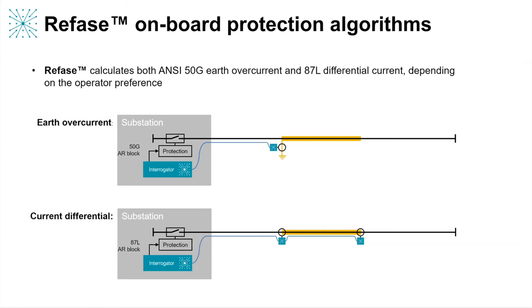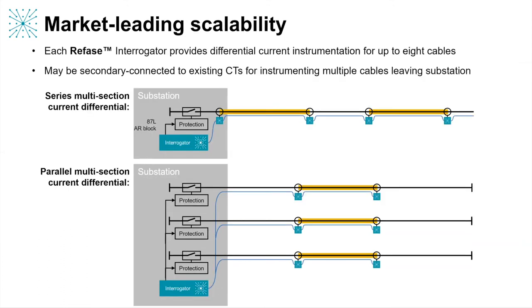The choice of one or other of these methods is up to the operator, and importantly we can provide either or both in a single scheme. To deploy one or other of these systems would only use a small portion of the total sensor budget available to each Refase scheme — that's 50 sensors per fiber over 100 kilometers of distance. So the system has market-leading scalability, which allows multiple series or parallel cable sections to be instrumented with a single system. Given this full budget of 50 sensors per fiber over 100 kilometers, we can provide full differential current monitoring of up to eight cable sections.